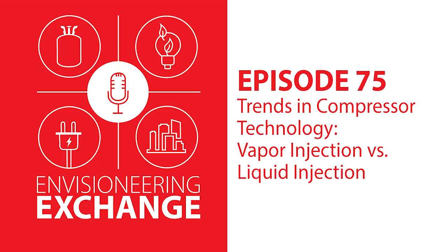You have a probe that's mounted on your compressor discharge line, and a controller that's reading the temperature and adjusting the valve based on the conditions. The way the liquid injection works is that when the temperature of that discharge line gets too hot, the valve opens and starts pulsing the liquid in to cool the compressor down, so you don't cook the oil, the bearings don't get burned out, the paint doesn't start to melt off the compressor shell, things like that.